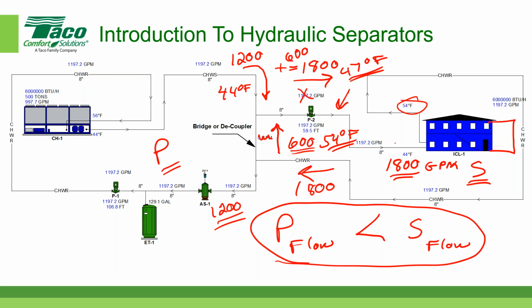As that primary temperature, 47 degrees, rises, we have less capacity out to our building, and potentially if the water temperature rises high enough, we run into the problem of not having the capability of doing dehumidification because our water temperature is too high. So whenever the primary flow is less than the secondary flow, we wind up with the flow across the bridge in the opposite direction, and we get the wrong temperature for the system. In this case, it starts to rise.